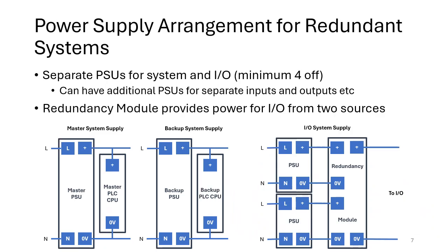Redundant systems often need more power supplies, and typically it's the power supply in the system that's the least reliable part, although that's arguable. So what you typically need in the redundant system is at least 2 power supplies, one in case of failure of the other power supply. They can back each other up. But again, to be able to separate the I/O system from the system supply, then you probably need even more power supplies. I'd recommend a minimum of at least 4 power supplies. But again, as before, you might have additional power supplies to separate inputs and outputs. Now for the system supply, if you've got 2 separate controllers, they can just have 1 power supply each.